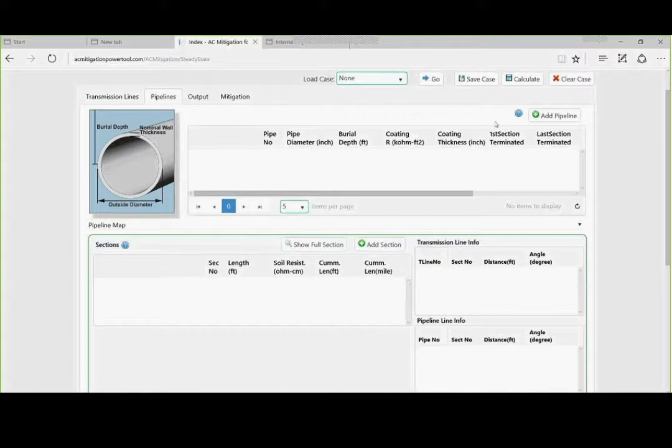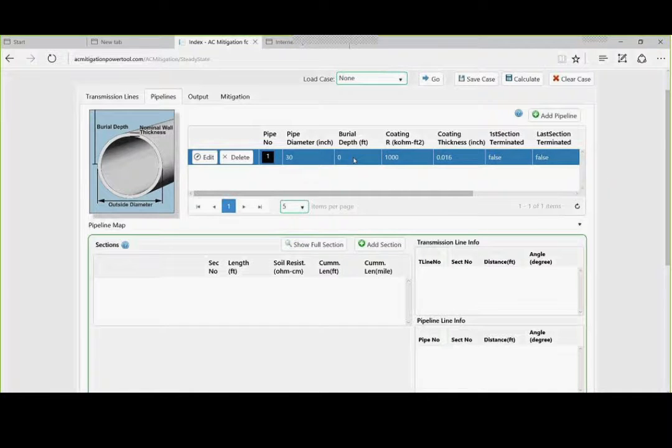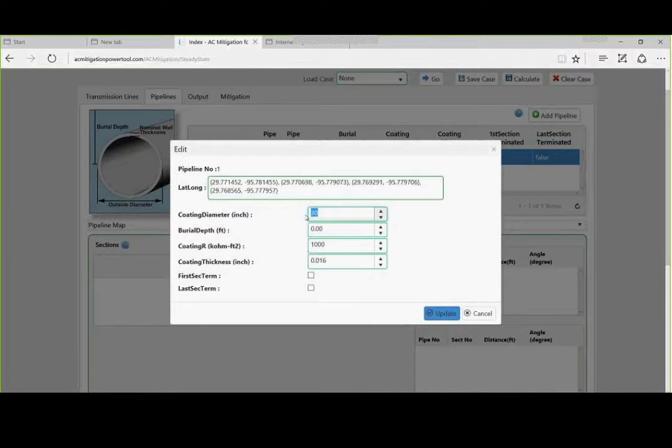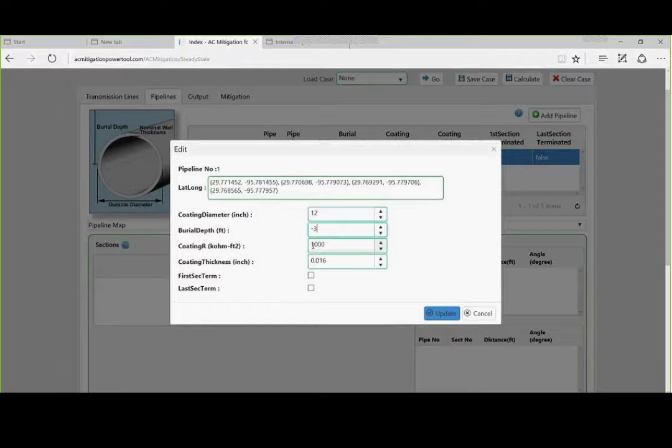And the first one we are going to add, we are going to add a pipeline. I am going to hit add pipeline to the right with a plus. And you notice it defaults to a 30 inch. We are going to edit it. And we are going to make this a 12 inch line. We are going to make it minus 3 feet burial depth. Another key component or primary factor is the coating resistance. And my suggestion is that you take measurements in the field to determine what that value is. And you can get that from the NACE standards on coating conductance.